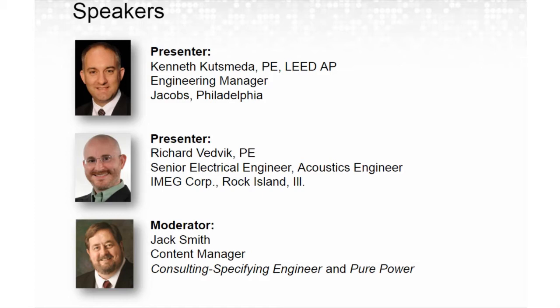I did have a slide that was talking about how transformer impedances will affect the available fault current on the secondary, and how that then affects what you're going to experience for arc flash. Taking that into consideration is really important. While it seems very alluring to use the lowest possible impedance rating on a transformer to reduce energy, and it's a pretty substantial reduction, the side effects of that might mitigate any benefit, and might also mitigate any cost when you associate that with the arc flash mitigation techniques that you have to go through.